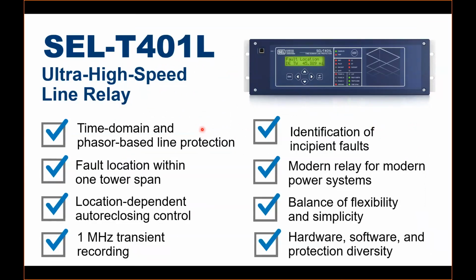It may be an overhead line, it may be a hybrid, or it may be a combination. On special applications like inverter-based generations, it may be hybrid installations, or maybe multi-terminal applications, compensated as well. So it is having the newer technologies with the phasor-based as well. And fault location guaranteed to 1 tower span, that is we guarantee plus minus 300 meters. And auto reclosing control, that you can have a very innovative auto recloser control if you have hybrid line applications. And the sampling is 1 megahertz.